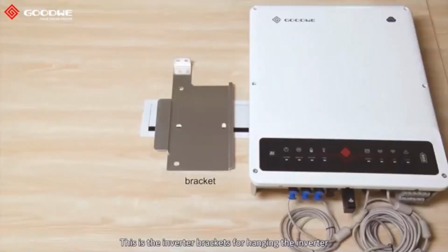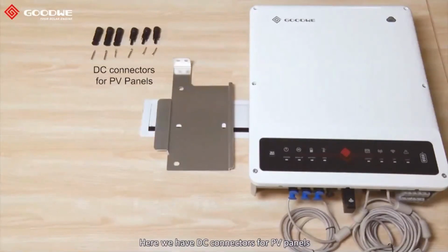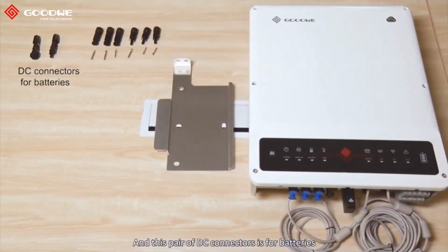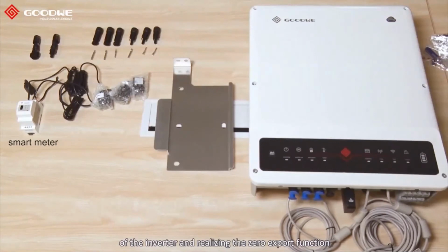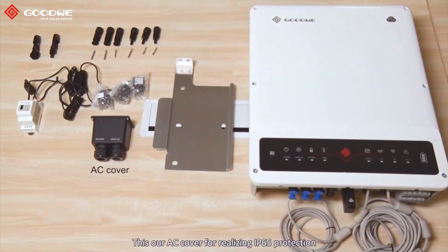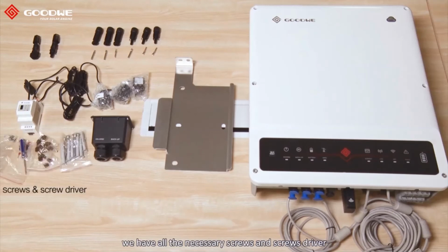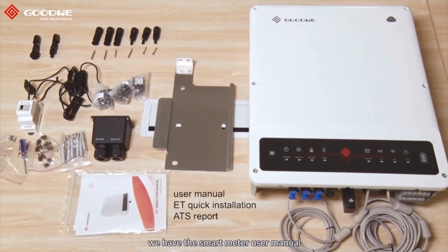This is the inverter bracket for hanging the inverter. Here we have DC connectors for PV panels, and this pair of DC connectors is for batteries. Here we have the smart meter for controlling the output of the inverter and realizing the zero export function, already connected with 3 CTs, all pre-wired. This is our AC cover for realizing IP65 protection. For installing the inverter, we have all the necessary screws and screwdriver. In the small transparent bag, we have the smart meter user manual, the ET inverter user manual, and the ET quick installation and ATS report.